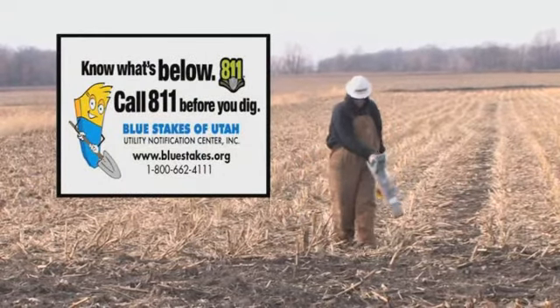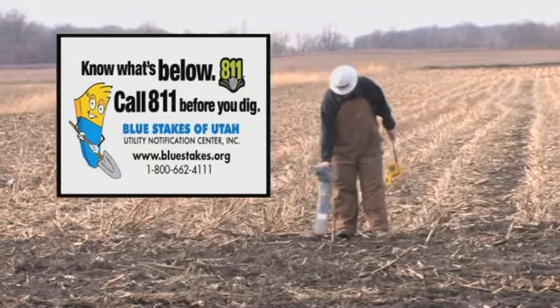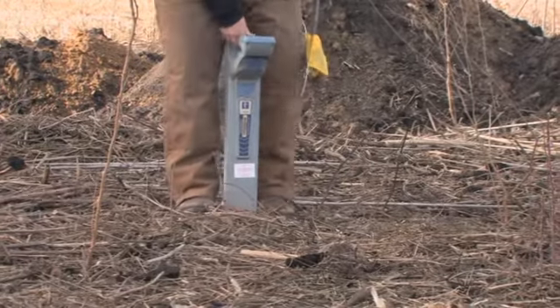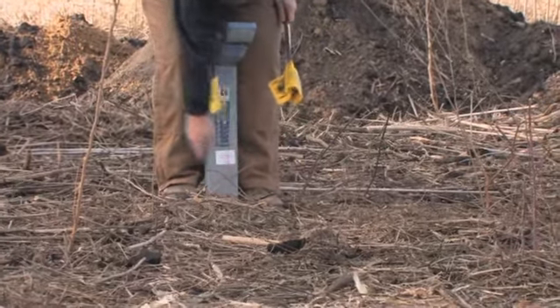While mechanical failure, corrosion, and human error all contribute to pipeline incidents, third-party damage is one form of pipeline incident that is virtually 100% avoidable. When excavators call 811 or contact their local one-call center online, the utilities in the vicinity of the excavation respond within a 2 or 3 business day time frame, and utility personnel equipped with electronic instruments mark the location of their underground pipes or cables.